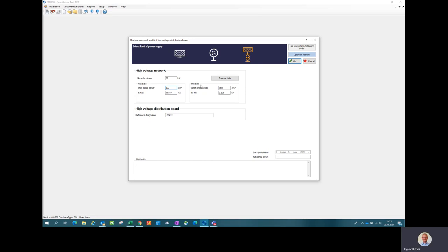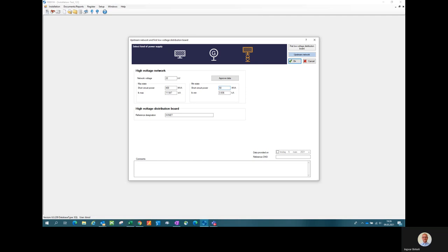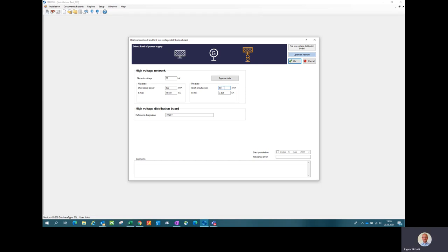It's very unlikely that short circuit power exceeds 400. For the minimum value of the short circuit power, you can go with 150 if you're close to a transformer station, or if you're a bit away or you don't know, you can choose a more conservative number here. Here I choose 50 as a very conservative number. If you're on an overhead line, a weak overhead line, far distant from substation transformer station, you might have to go down to 20 or 15. But in most cases 50 is a good number for the minimum state.